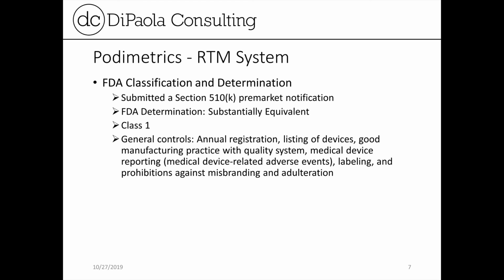Next, let's talk about FDA approval. Podimetrics filed a 510(k) pre-market notification with the FDA. The FDA then came back with a substantially equivalent determination and gave them a Class 1 rating. This is very significant because it means that they don't have to spend potentially years providing additional information in the way of clinical studies, validation, capability studies, and so forth. Instead, they can do what's called general controls, which is an annual registration. You list your device with the FDA. You have to have good manufacturing practices with a quality system, and you have to report any medical device related adverse events. You have to ensure that your device is properly labeled, and there are prohibitions against misbranding.